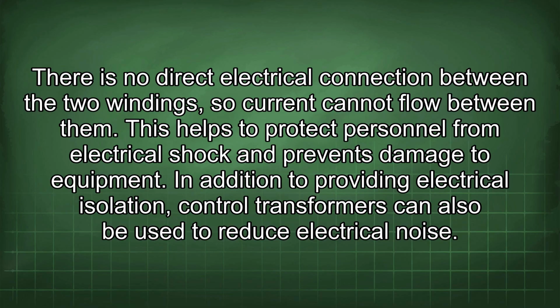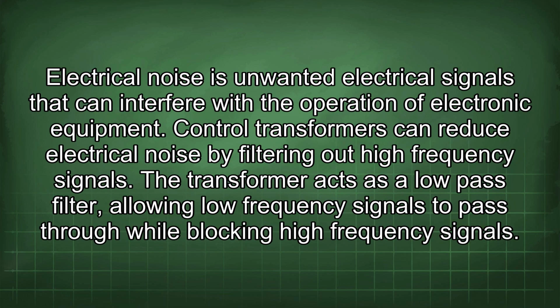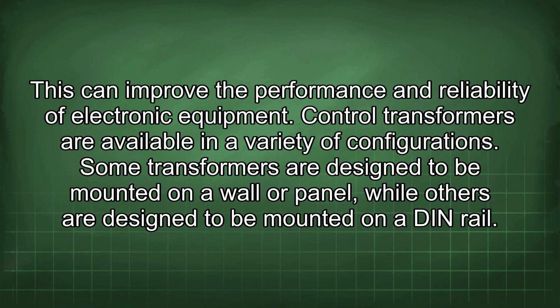In addition to providing electrical isolation, control transformers can also be used to reduce electrical noise. Electrical noise is unwanted electrical signals that can interfere with the operation of electronic equipment. Control transformers can reduce electrical noise by filtering out high-frequency signals. The transformer acts as a low-pass filter, allowing low-frequency signals to pass through while blocking high-frequency signals. This can improve the performance and reliability of electronic equipment.